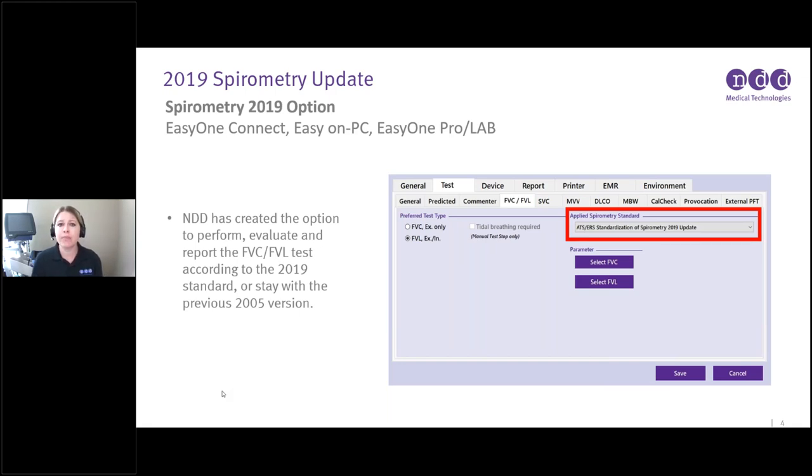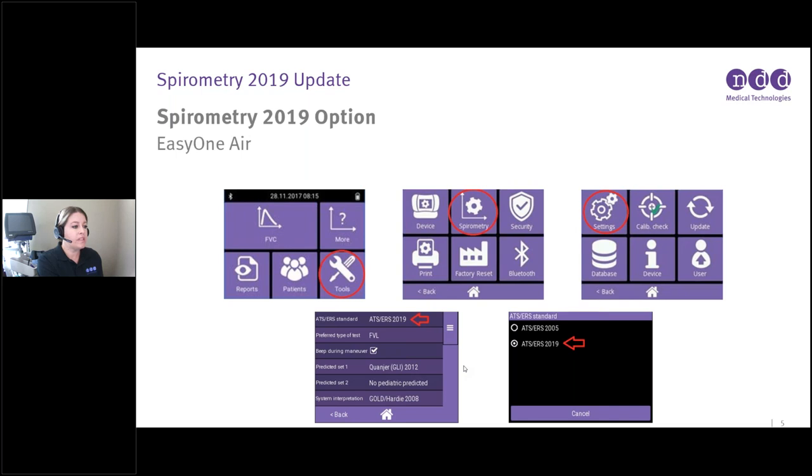Once your software is updated, it will prompt you on restart which option you want. If you're not sure, you can go into the Utilities menu on EasyOne Connect, Easy on PC, or EasyOne Pro and ProLab and select your desired Applied Spirometry Standard under Test > FVC/FVL. On the EasyOne Air, that option is under Tools > Spirometry > Settings, where you choose either ATS/ERS 2005 or 2019.